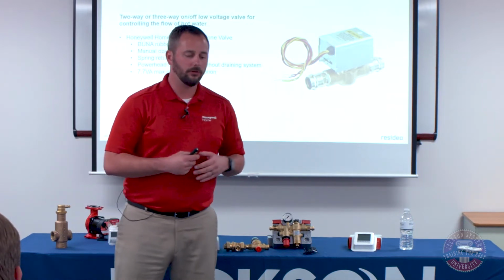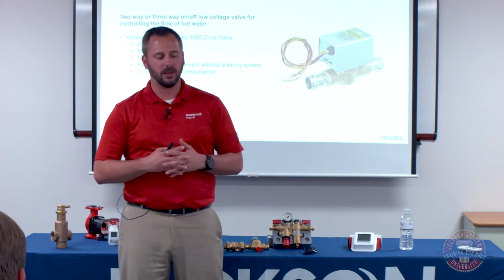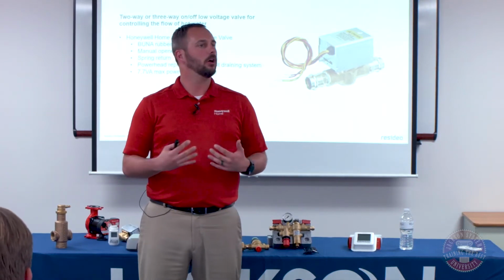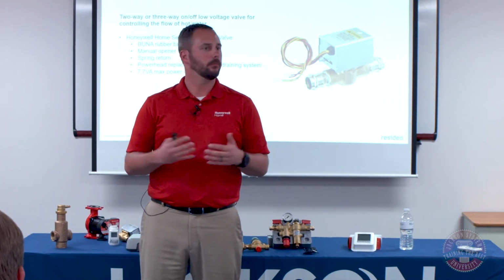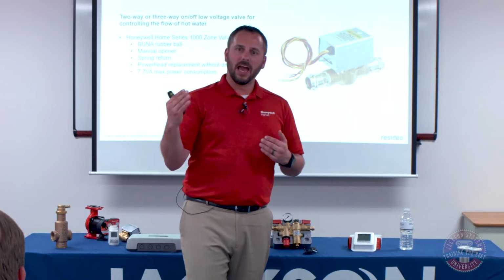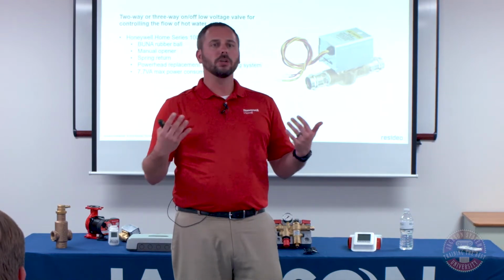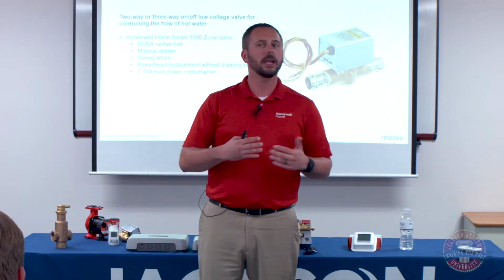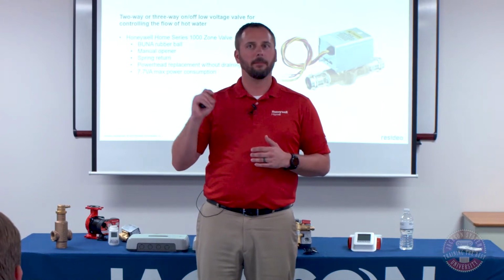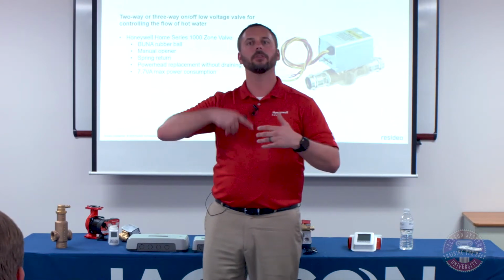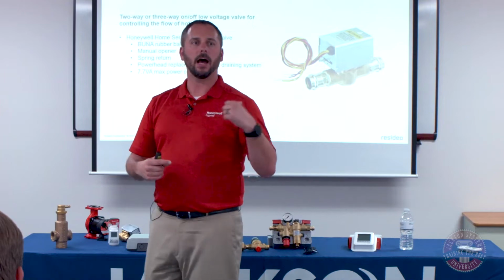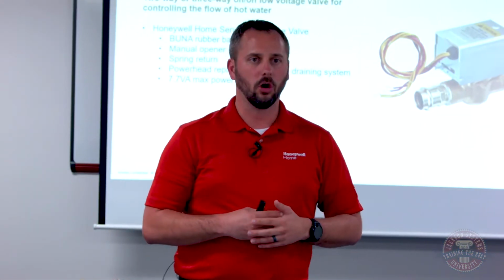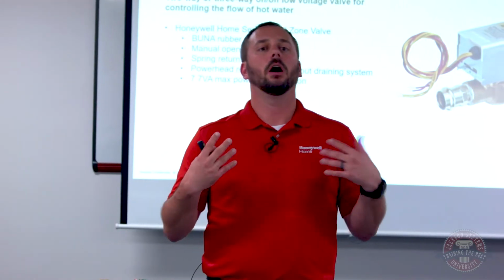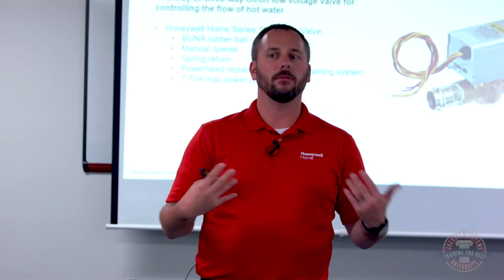So what these are, zone valves, just from a top-level standpoint, are normally closed water valves. So they have a spring inside of them that keeps them shut. You give it 24-volt power on a call for heat, and it opens them up. So unlike a pump where you throw 120 volts to it and it starts basically running, with a valve, you just give it 24 volts, it opens up, and you use a third-party control. I'll show you our controls later, that tells it to open, and then you get flow through to the system.